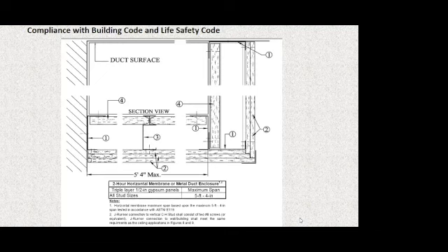So what's actually been tested and approved for use in the wild is actually an L-shaped assembly that's constructed around a duct that's been tucked up in the corner of a 2-hour wall and a 2-hour floor slab. That's as good as it gets when you start using drywall.